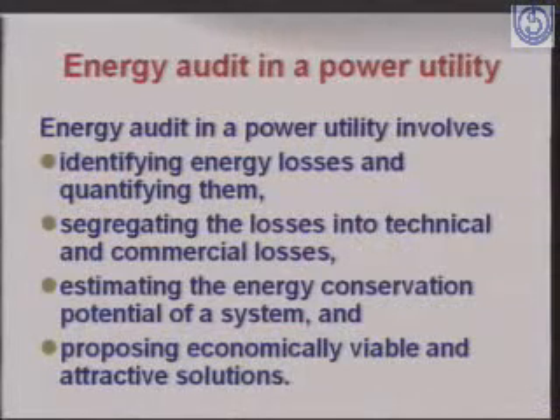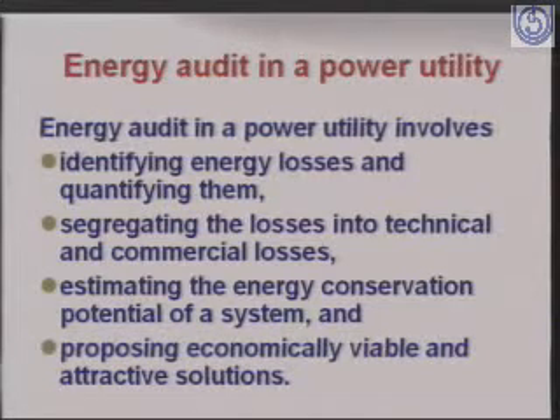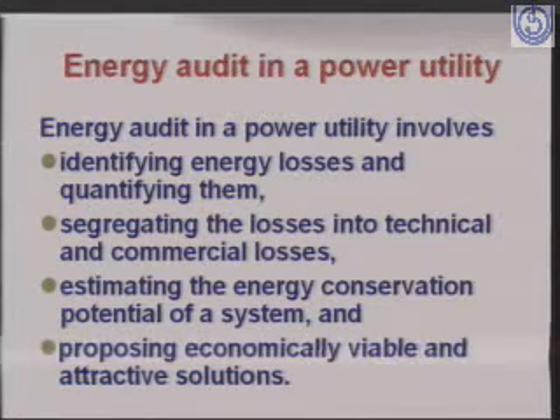Now let's come to our main area: how to conduct an energy audit in a power utility. Basically, it involves identifying energy losses and quantifying them, then segregating these losses into technical and commercial losses, then estimating the energy conservation potential, and finally proposing economically viable and attractive solutions. Prior to the energy audit, many consultants, plant people or distribution system professionals were carrying out studies, but those studies were simply energy conservation studies, where one component of the total system was picked up and then a potential was projected, which was totally wrong.